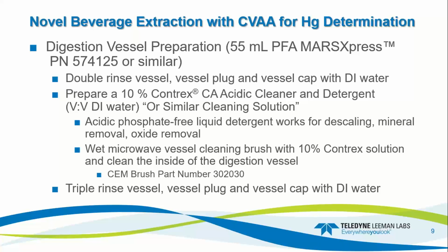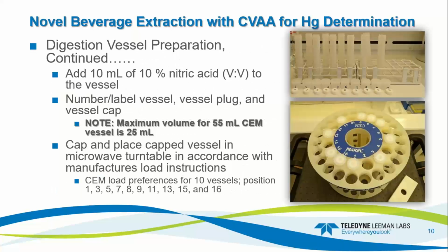Acidic, phosphate-free liquid detergent will work for descaling, mineral removal, and also oxide removal. I wet the microwave cleaning brush with 10% Contrex solution and cleaned inside the vessel. I used a CEM brush, part number 302030, and then triple rinsed the vessel plug and vessel cap with DI water after you've given the inside a good brushing with the cleaning brush.